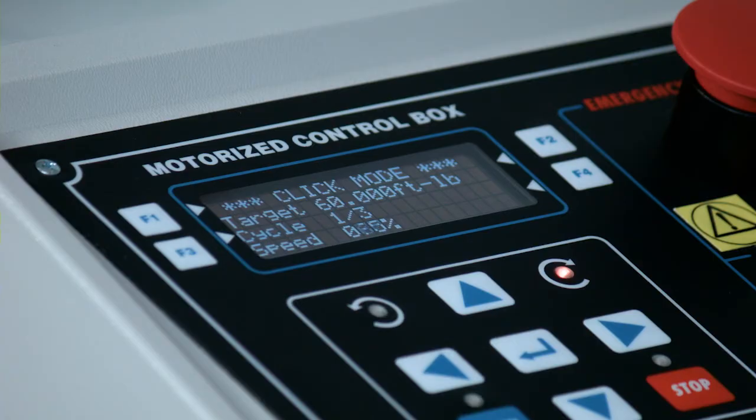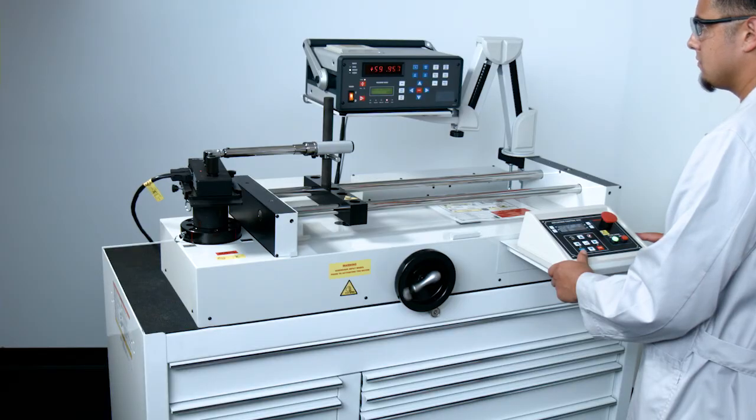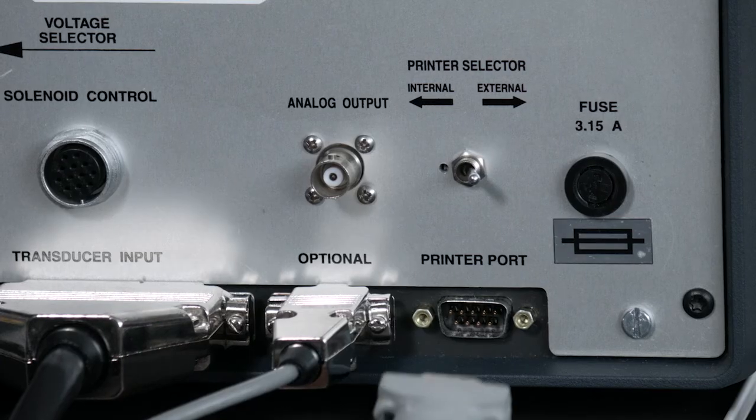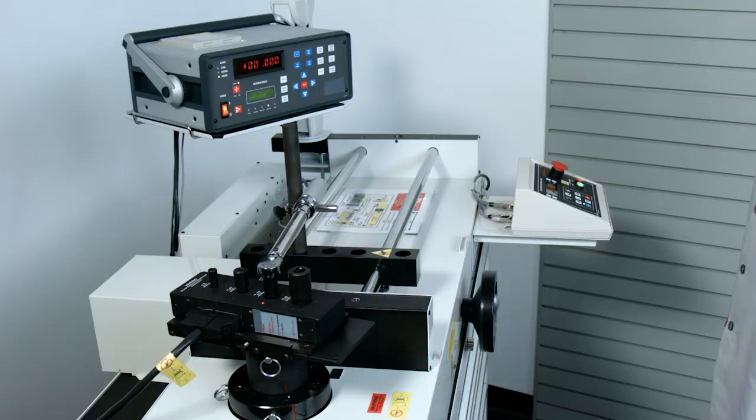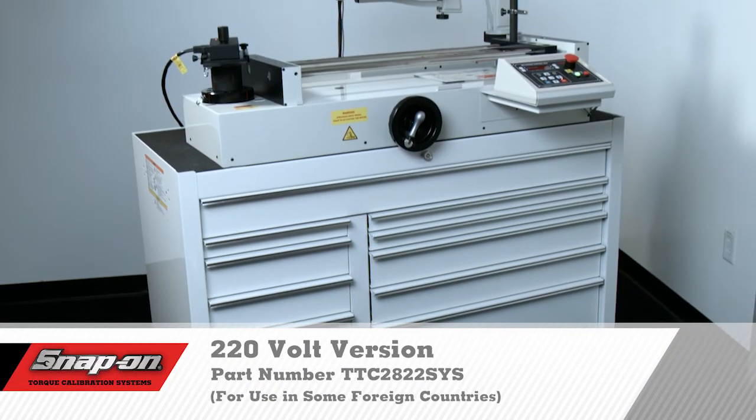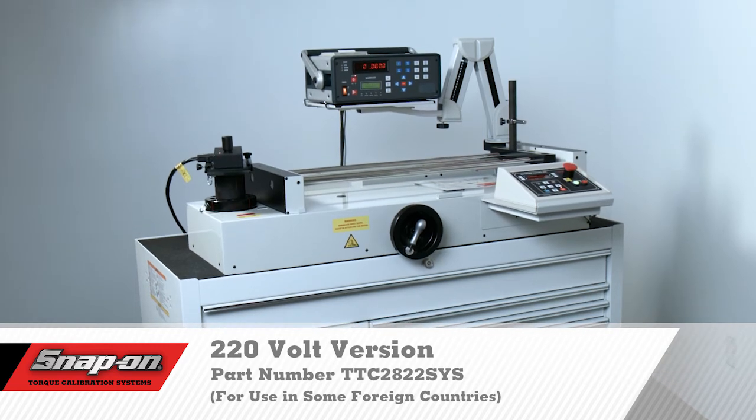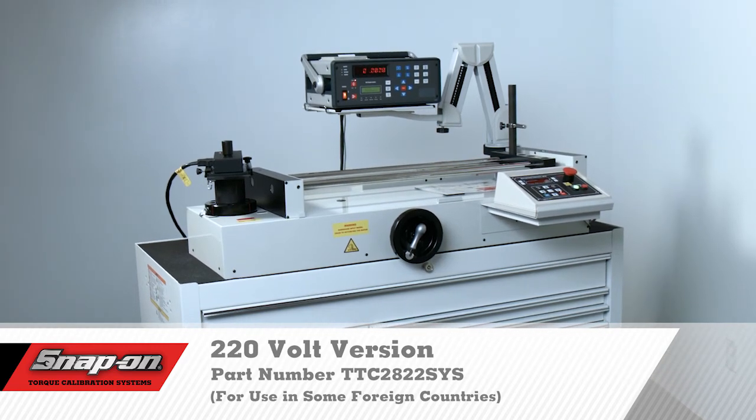The system operates in both the clockwise and counter-clockwise directions. Once all checkpoints have been reached, the stored data may be downloaded to a PC and used for printing torque calibration certifications. The motorized calibration system is also available in a 220-volt version, part number TTC-2822-SYS.